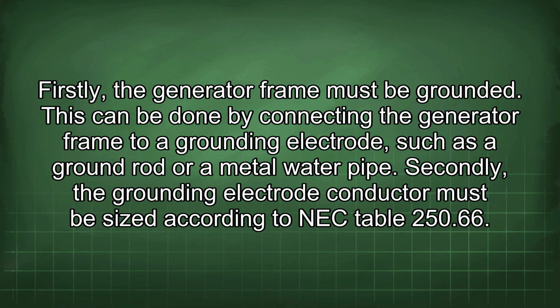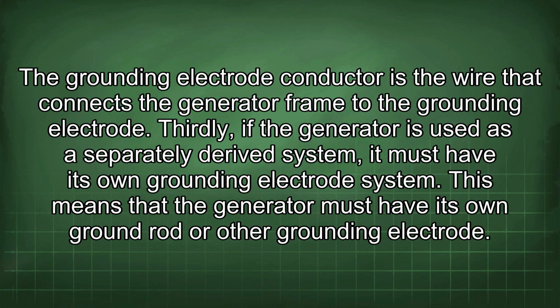Secondly, the grounding electrode conductor must be sized according to NEC Table 250.66. The grounding electrode conductor is the wire that connects the generator frame to the grounding electrode. Thirdly, if the generator is used as a separately derived system, it must have its own grounding electrode system. This means that the generator must have its own ground rod or other grounding electrode.